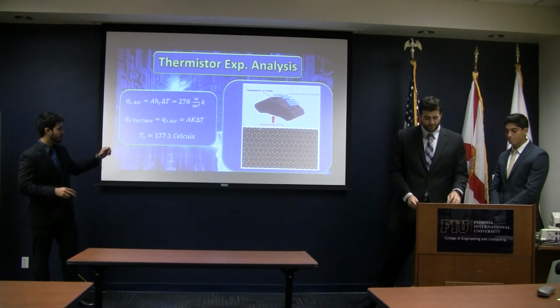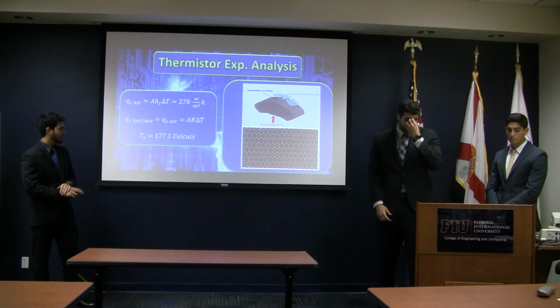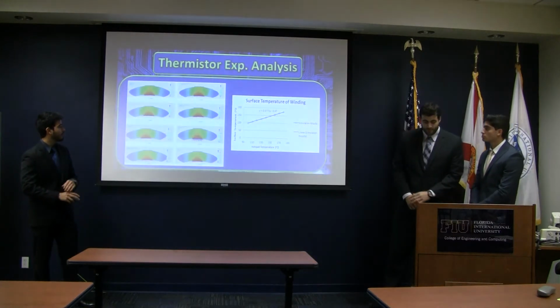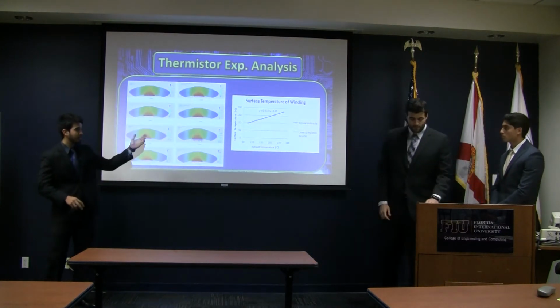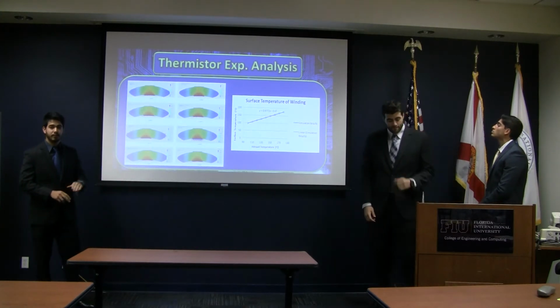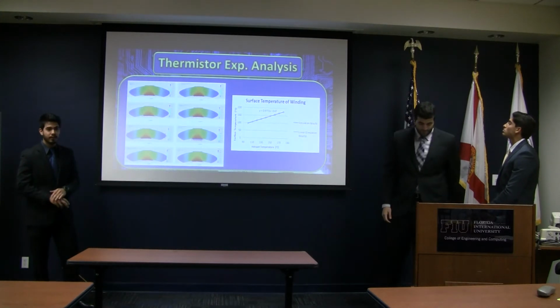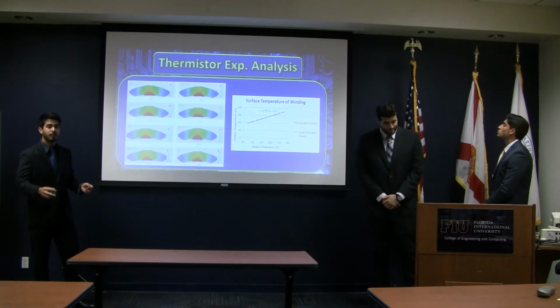We did first manual calculations, and we also did simulations, and we finally were able to calculate a trend line for the difference between the outside and the inside temperature of the winding. That way, once again, we catch the hottest part of the winding.